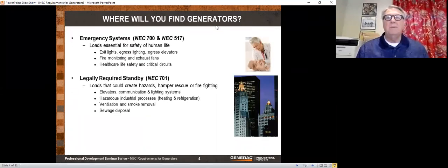All right, let's talk about emergency systems. Emergency systems are loads essential for safety of human life. So if somebody could die as a result of that generator failing or not being there, then we call that generator an emergency generator. Now you have to be careful because a lot of people refer to all generators as emergency, and the EPA has different terminology than the National Electrical Code for what emergency generator means. But in the National Electrical Code, it means that somebody's life is on the line.